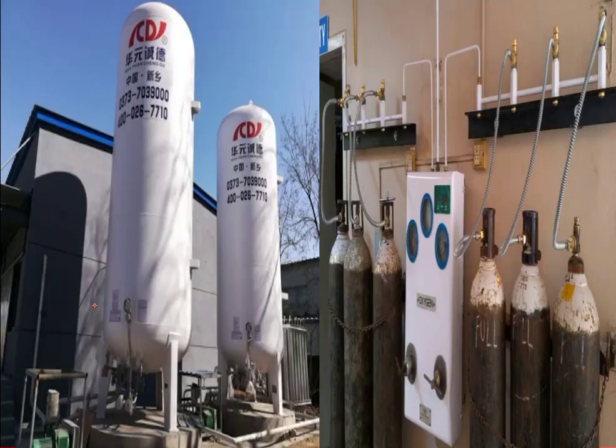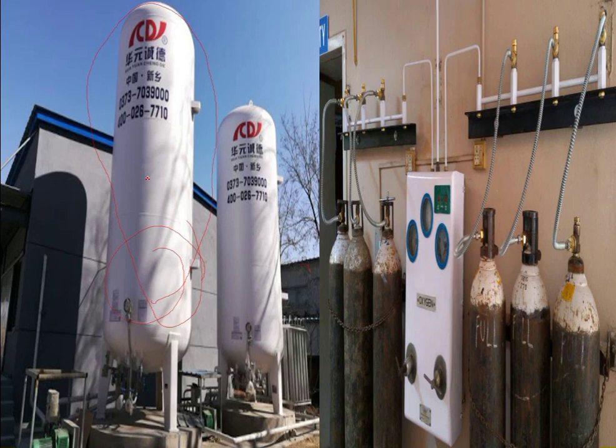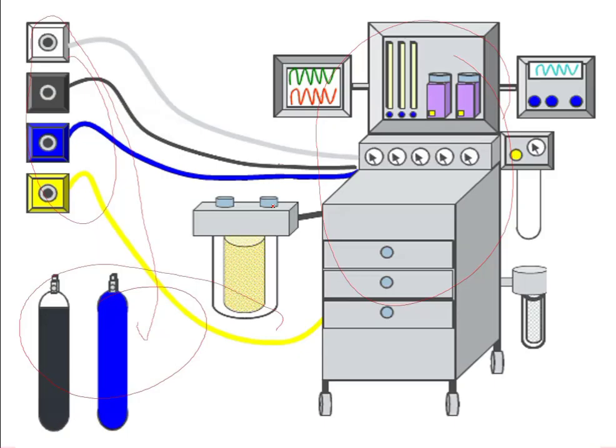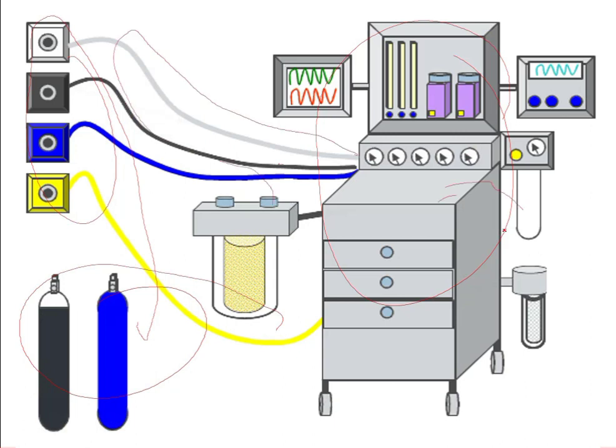So, where do the pipelines get their gas supply? We have many tanks of gases at the backyard of the hospital. For example, the oxygen tank contains liquid oxygen which is converted into oxygen gas to supply the pipelines, and from the pipelines to the anesthesia machine, and from the anesthesia machine through the anesthesia circuit to the patient by positive pressure ventilation.